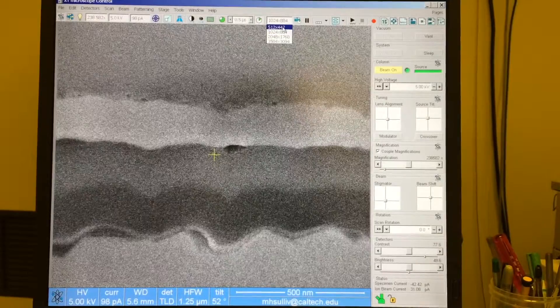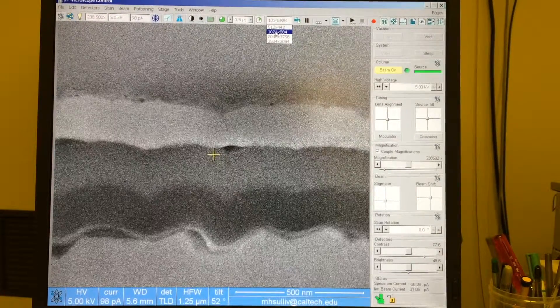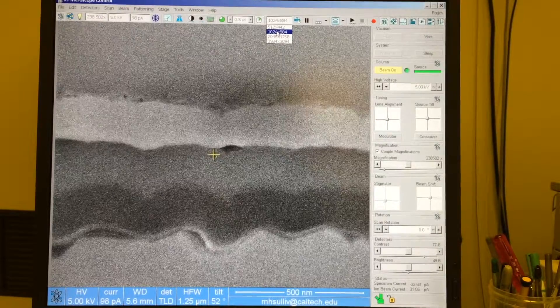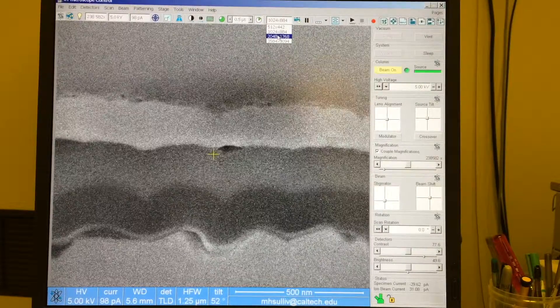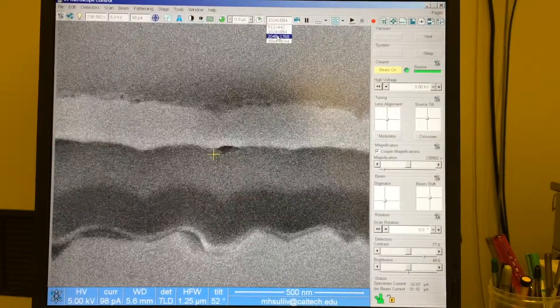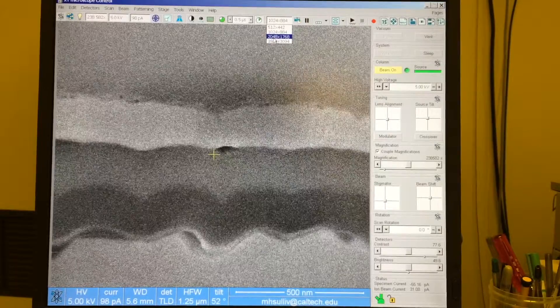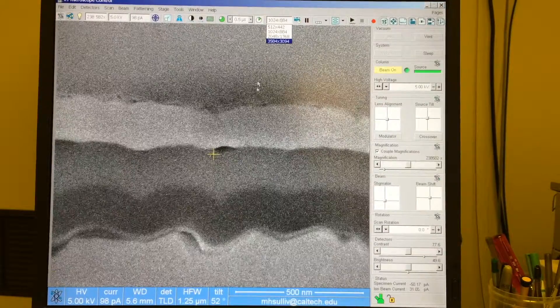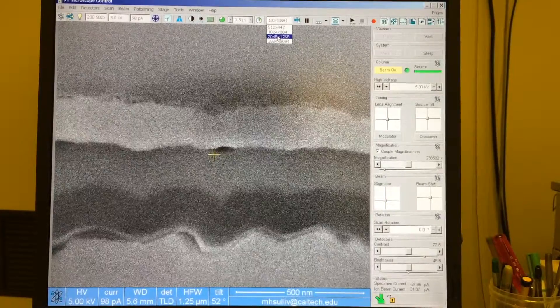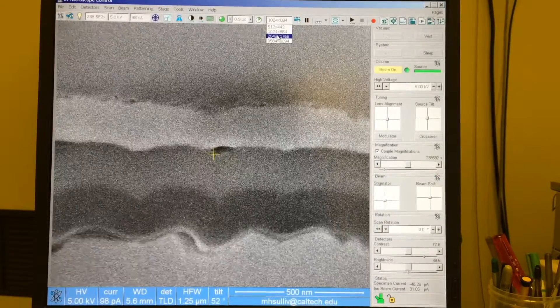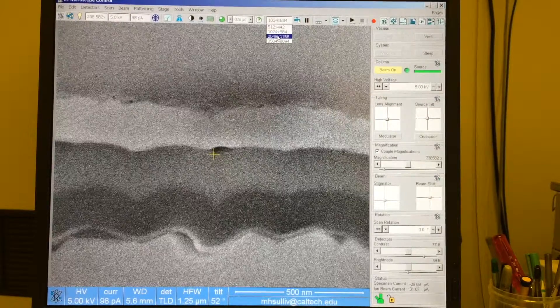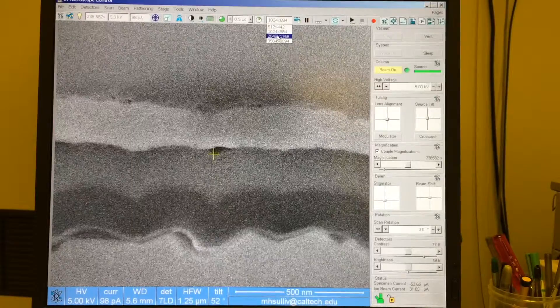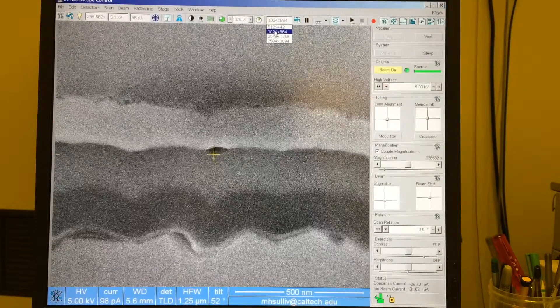We also want to select the number of pixels for our image. In this case, something like 1024 will probably be all right. If you're trying to publish the image, journals often want higher pixel density, so they have a higher dots per inch value. In this case, if we go to 2048, when we're down around 1 micron HFW, that's going to mean each beam step is sub-nanometer in position. You're actually going to start pushing up against the resolution of where the beam can actually be placed by the microscope's boards. So in this case, I probably would stick at 1024 at this high of a mag.